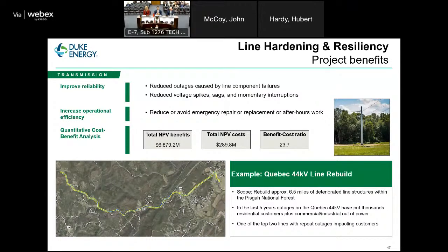Beyond the obvious benefits of taller structures, Mr. Guyton earlier talked about collateral damage: when a tree falls on a wood pole with aged conductor, you often get damage and breaks. When we rebuild with steel poles and new high-strength steel conductor, we're much less likely to have equipment damage—we can remove the tree from the line, re-energize, and restore. That means less outage time and less cost, ultimately benefiting customers.